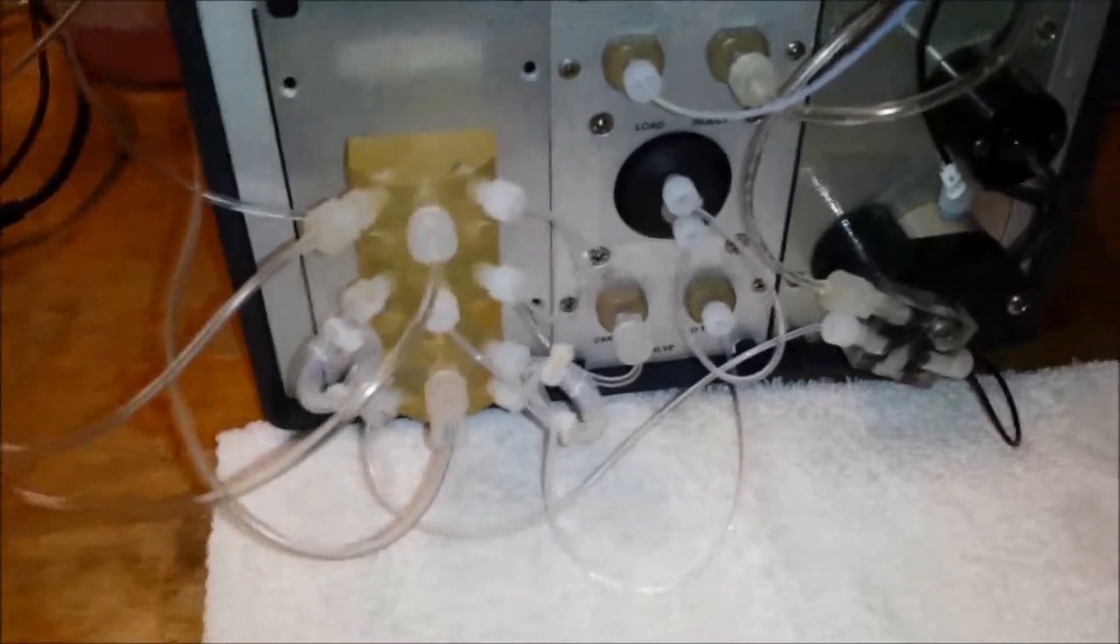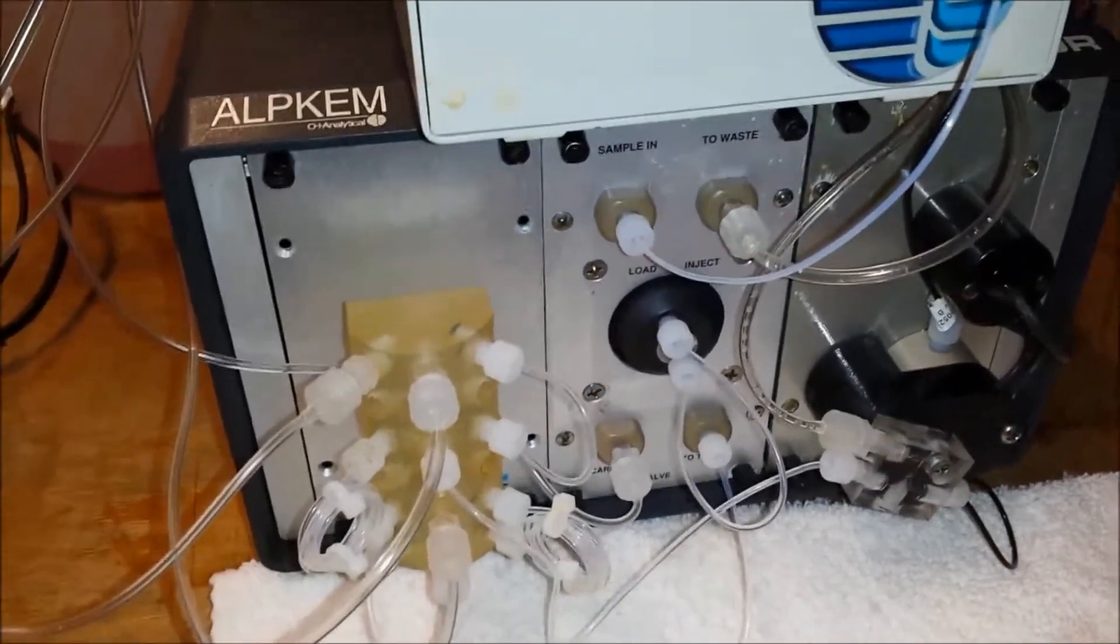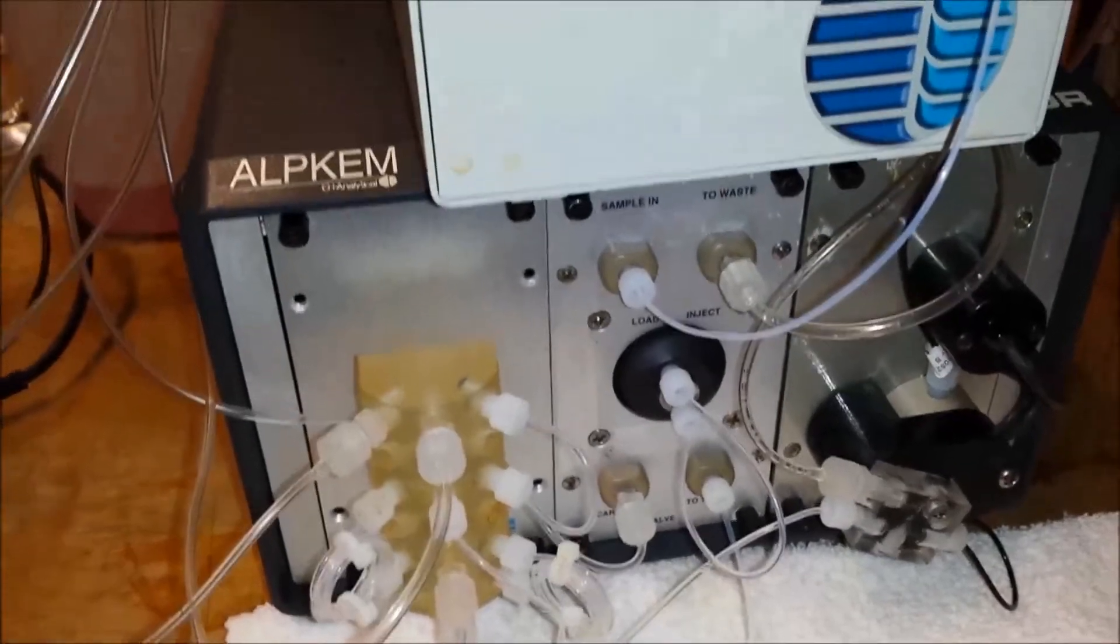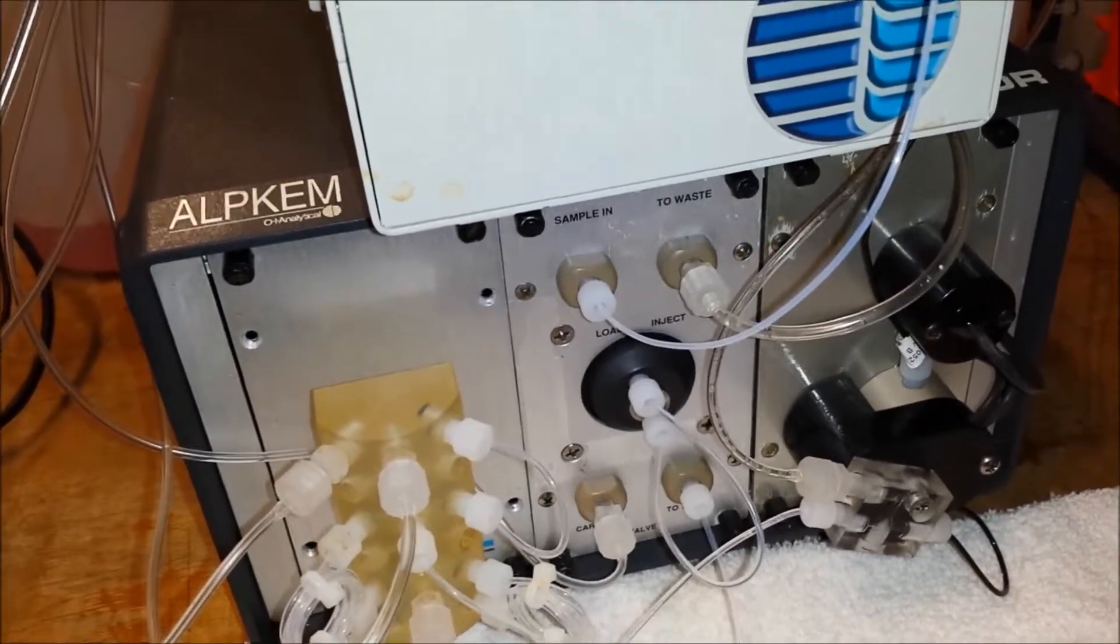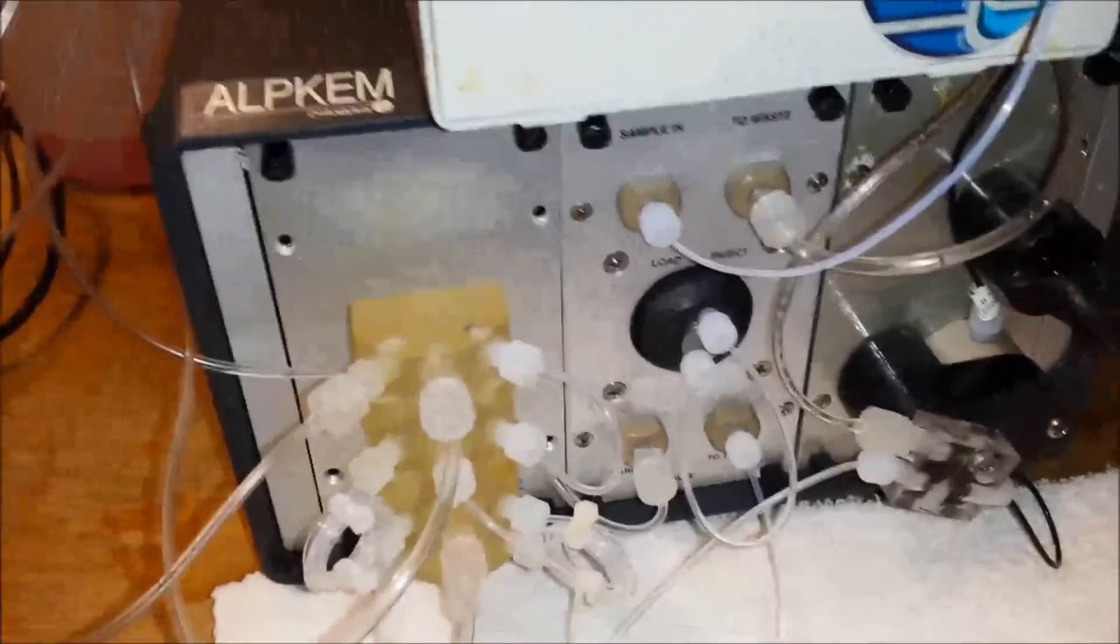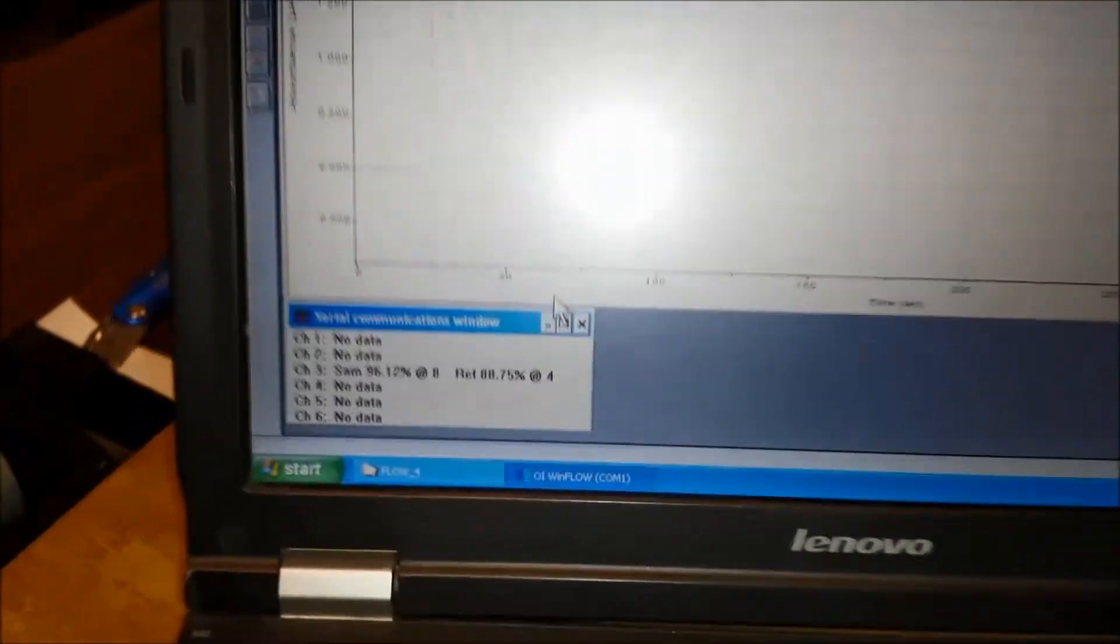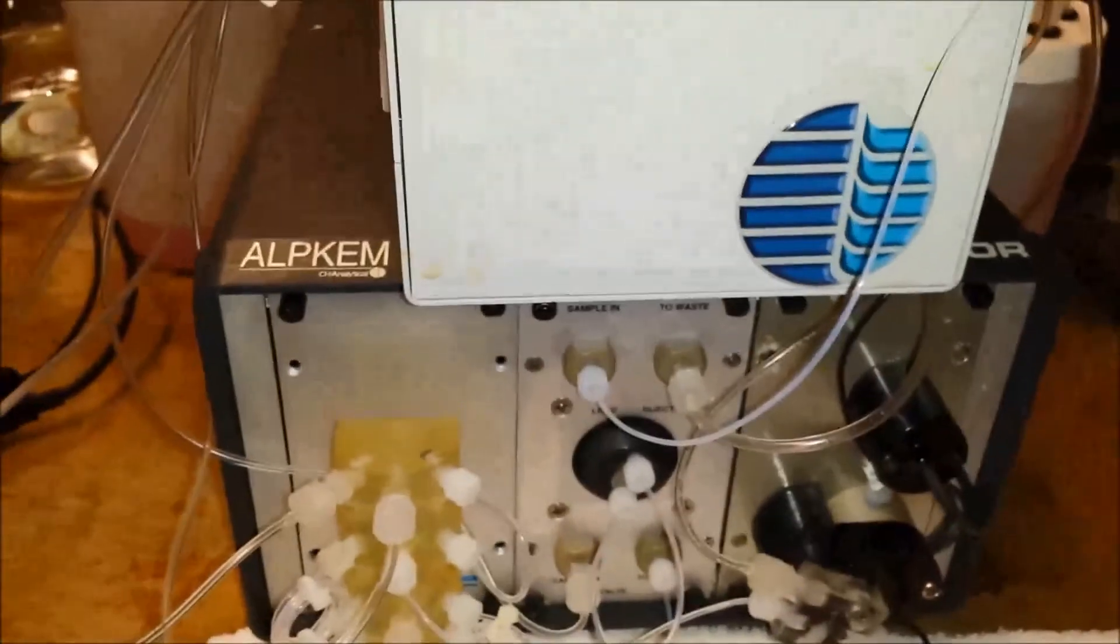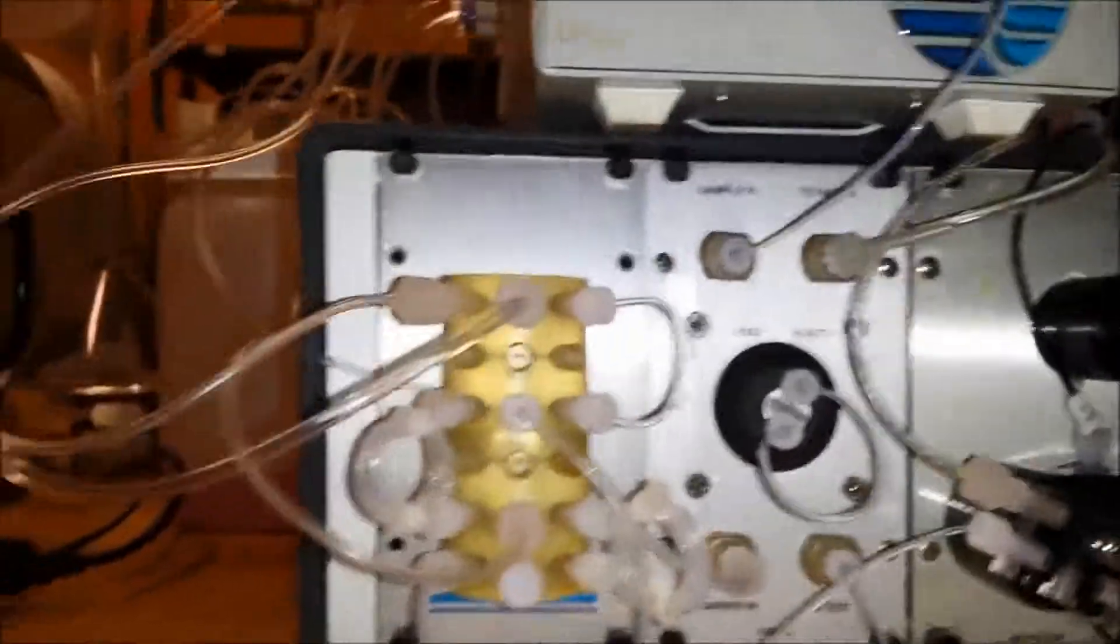If we have injected air from the loop into the system and we know that the probe and the sample tube and everything is coming into the cartridge, and we have checked the serial communication value and know that it is correct, and we know that our detector is on because you can see the light of the lamp.